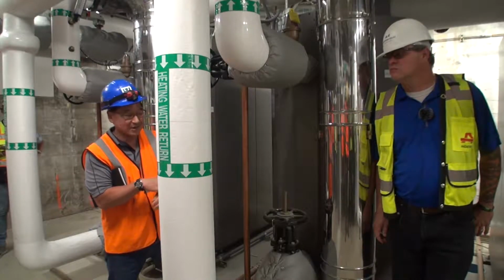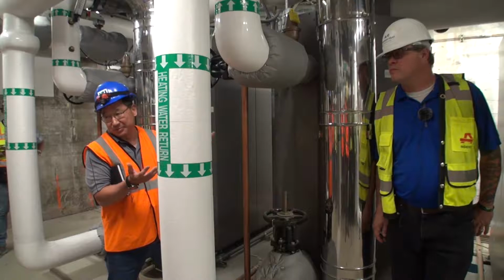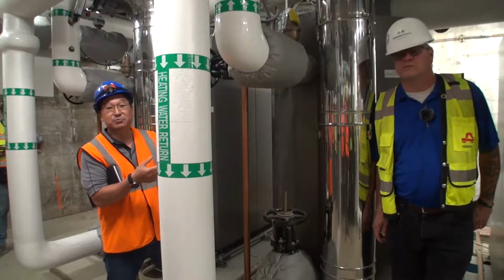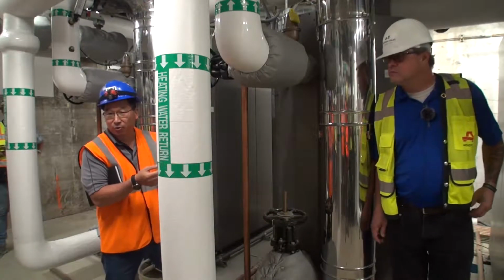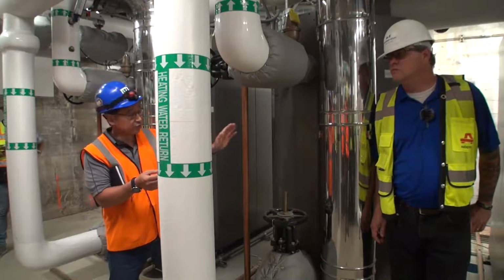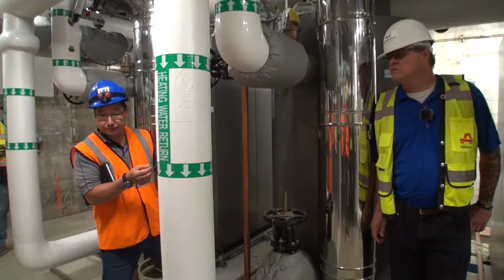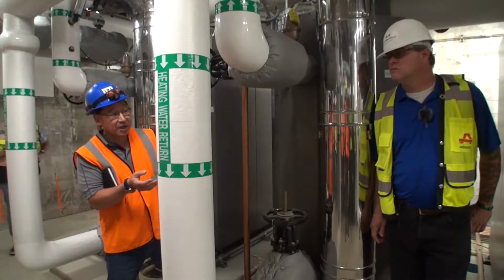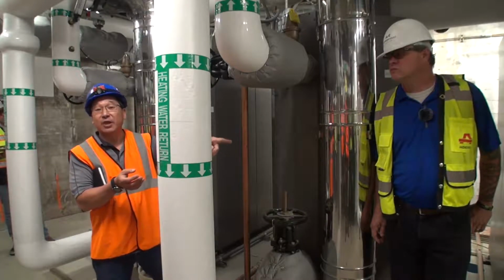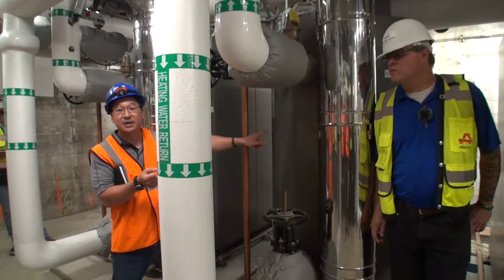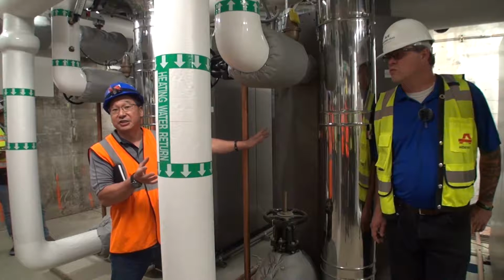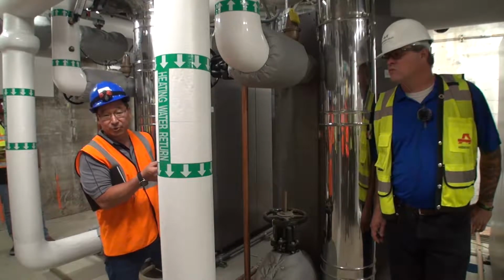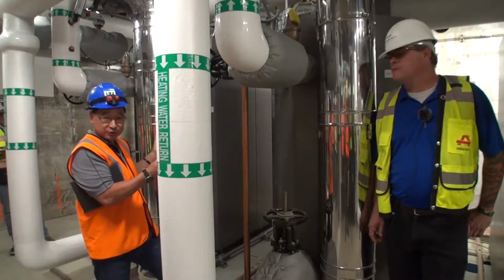It's not that much more money. The sensor is, I don't know, $150 plus a little bit of labor, a little bit of programming. We can throw the programming in. But if 2 or 3 is out and you do turn it off, as long as the master's on, we're okay. It'll realize that boiler number 2 is gone. It can't see it anymore. It can only see boiler number 3. So you only have the capacity of the 2.